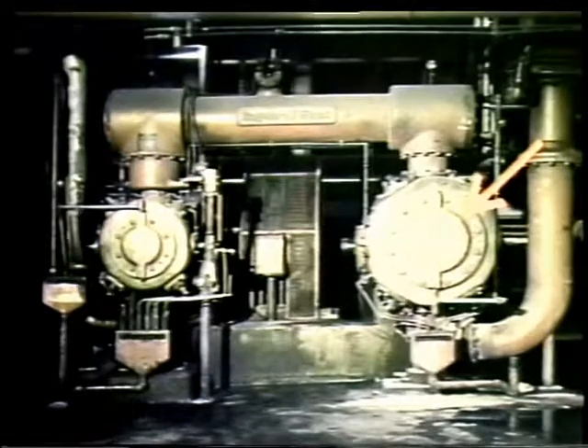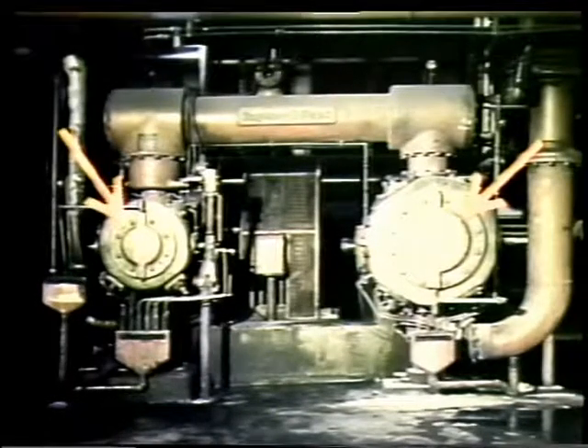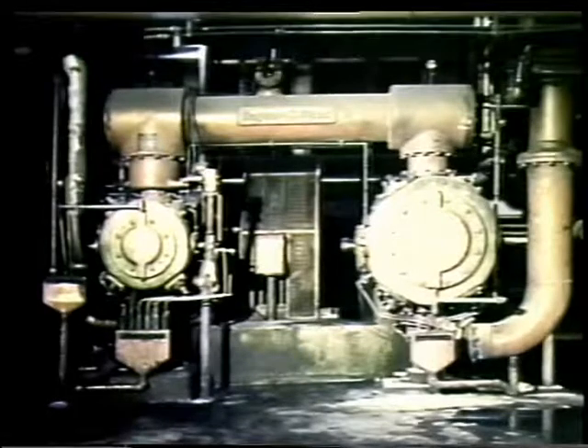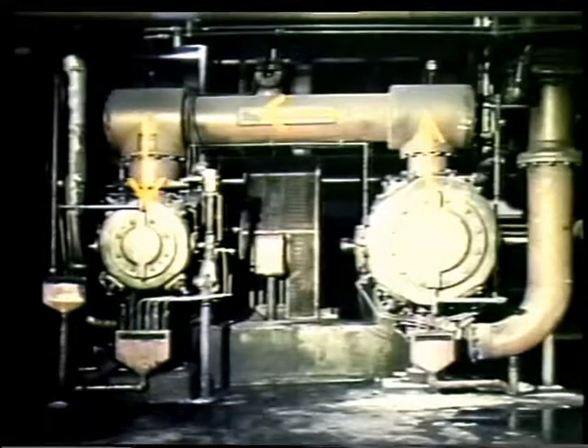After the first cylinder compresses the air, a second, smaller cylinder compresses that air again, giving it a higher discharge pressure. In our discussions, we'll use one cylinder to describe the operation of the compressor. Both cylinders are identical except for their size. This arrangement is called a two-stage layout. The discharge of the first cylinder leads to the second stage cylinder, where it is compressed again before it is discharged from the unit.